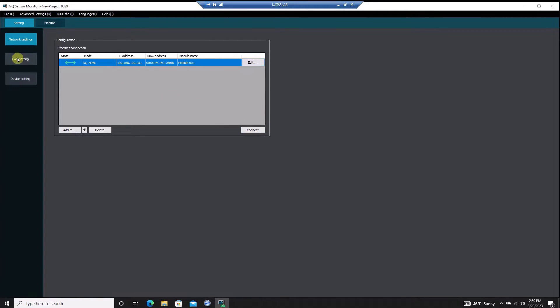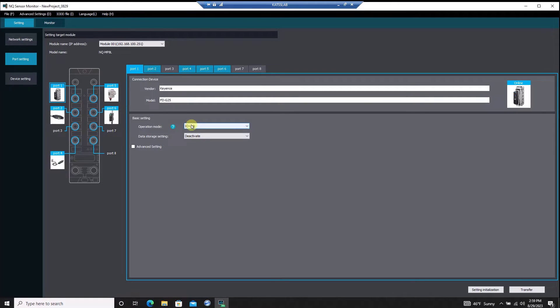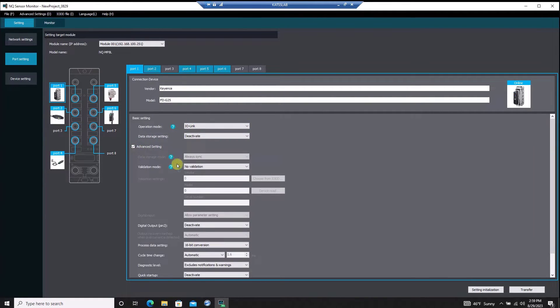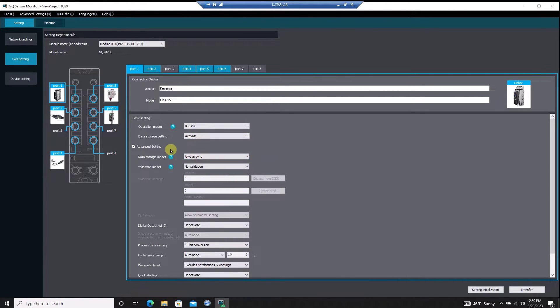In the port settings menu, I can configure the operation that each port is performing, along with some extra functions like data storage modes that back up IO-Link sensor data, and sensor validation settings for each port.